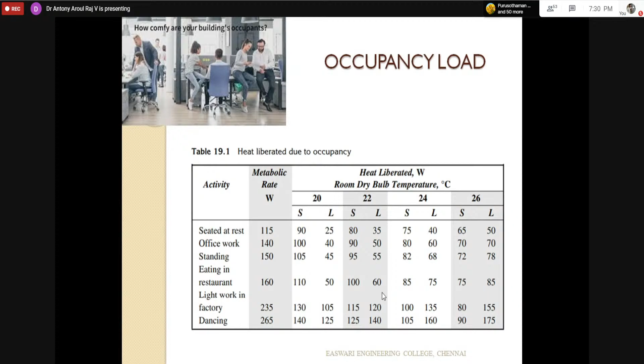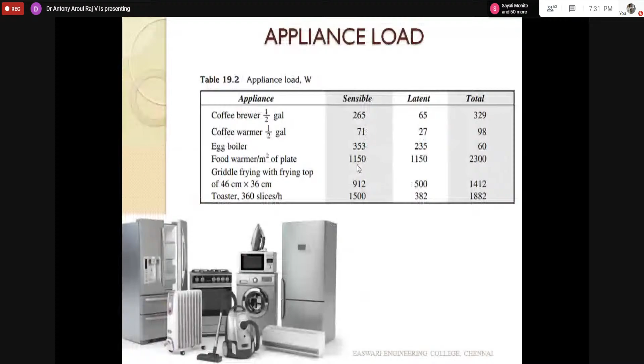This is for occupancy load—for whatever condition, you can pick these values and put them into the sensible and latent portions. Next is appliance load, which depends on capacity, giving a sensible load and sometimes a latent load. Cooking equipment will have latent loads also, while motors and computers add sensible heat only. This appliance load is part of the room load.